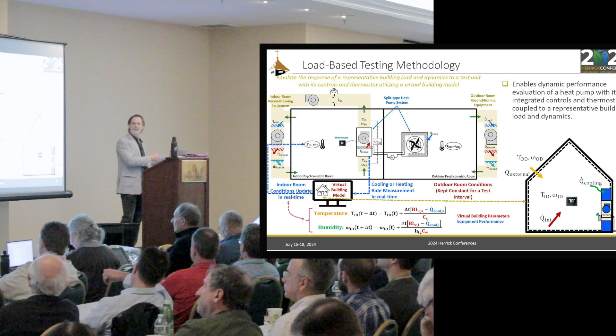In cooling mode, there's also a virtual building model for humidity. So instead of holding it at a specific wet bulb temperature inside, you actually let it manage the humidity in the space. And all this is done in real time on a 10-second basis, and you let the thing run for anywhere from an hour to up to maybe 4 hours, depending on how the unit is behaving.